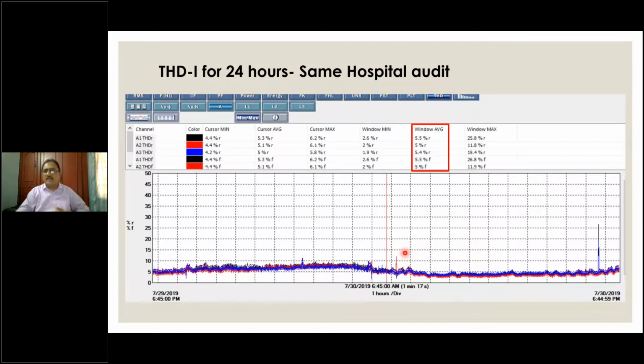Same hospital, same one full day window. Let's look at the harmonics. When we capture the harmonics, we look at the THD-R value, because the meter which I am using does not measure the TDD, but it is always possible to mathematically derive TDD from this THD value. Now this THD is based on the fundamental current, first order current. If I know the last 12 months average current, we will be able to convert this using an Excel sheet to TDD and report to the customer.